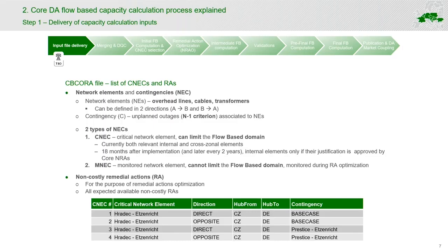The last input file is the so-called CBCORA file. It is a list of critical network elements with associated contingencies and also a list of non-cost remedial actions. By network elements, we mean overhead lines, cables, and transformers. By contingencies, we mean unplanned outages which are associated to those network elements — in other words, fulfilling the N-1 criterion. On the lower part of the slide, I present an example of such a network elements list.